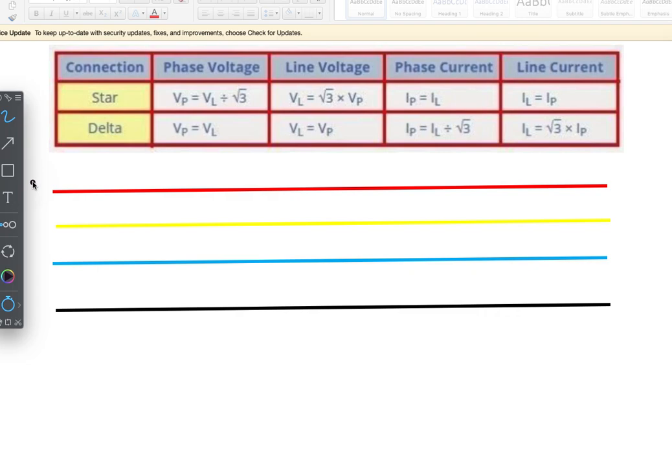Okay, so if we've got three lines here, line 1, line 2, line 3, and a neutral. This is typical of maybe the lines coming down your road, and then we generally have one phase into a house. So we bring a neutral into a house and maybe this phase, and then your neighbour might take the next phase and your other neighbour take the next phase. So we all have single phases, and that gives us 230 volts between a single phase and a neutral.